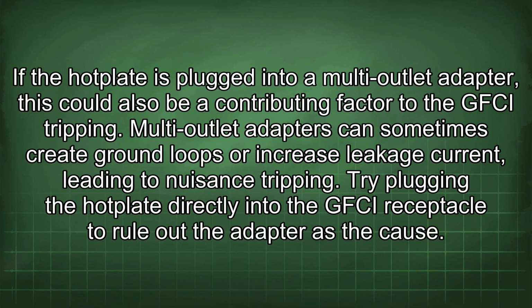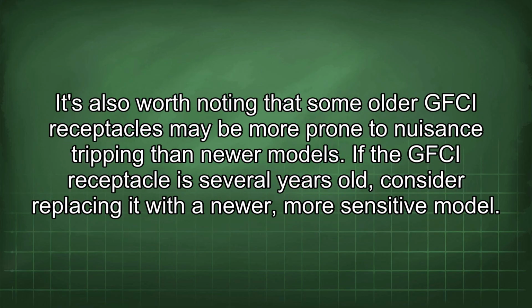If the hotplate is plugged into a multi-outlet adapter, this could also be a contributing factor to the GFCI tripping. Multi-outlet adapters can sometimes create ground loops or increase leakage current, leading to nuisance tripping. Try plugging the hotplate directly into the GFCI receptacle to rule out the adapter as the cause. It's also worth noting that some older GFCI receptacles may be more prone to nuisance tripping than newer models. If the GFCI receptacle is several years old, consider replacing it with a newer, more sensitive model.